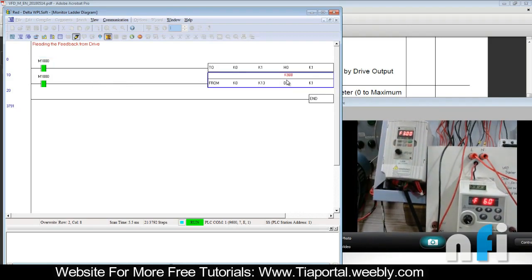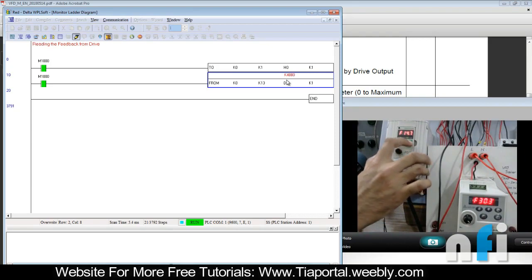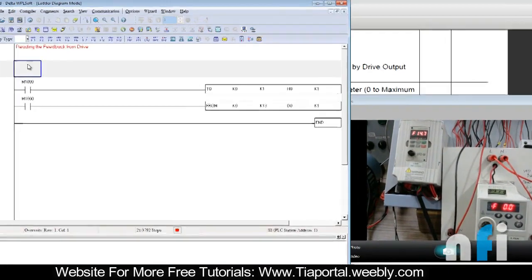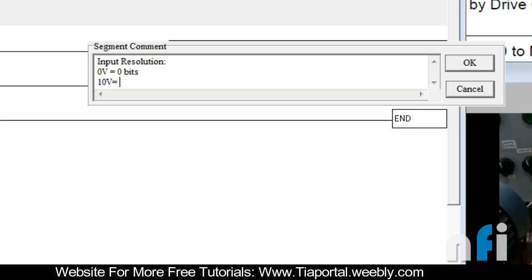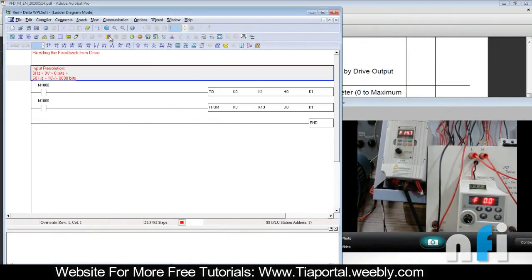The reading is twice because the gain is still set to 200%. If you increase to 10 Hz you will get a proportional feedback. For the PLC analog input card resolution: reading 0 volts gives 0 bits, reading 10 volts gives 8000 bits. So 0 Hz gives 0 volts which is 0 bits, and 50 Hz gives 10 volts which is 8000 bits on this card.